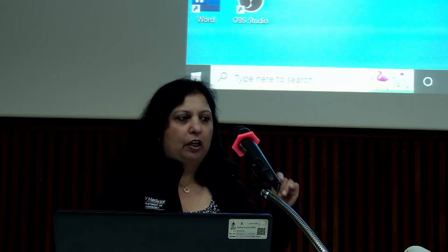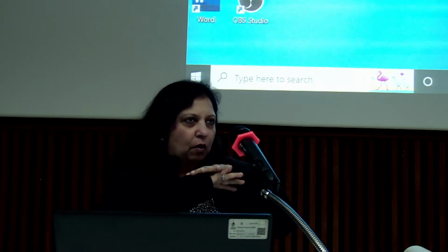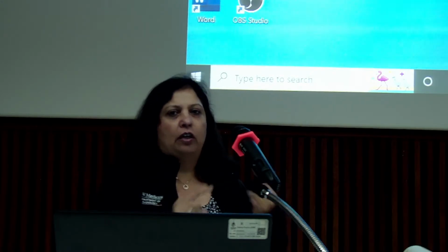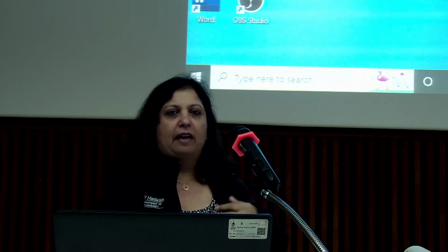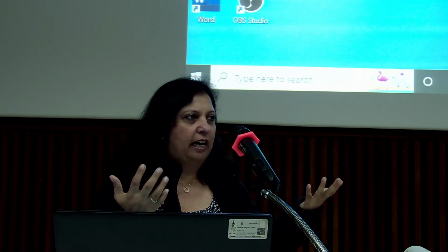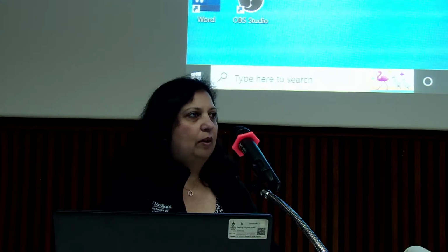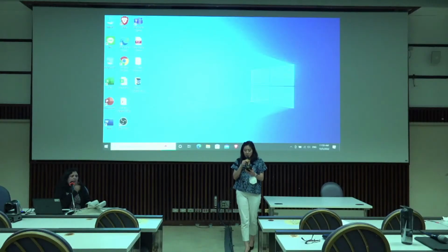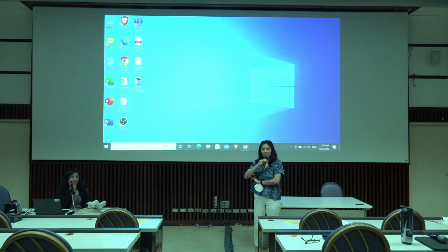There's a very good publication, NCRP 168, that's very detailed on how you can pick your thresholds, what reactions to expect, and what you should do. It's freely available, at least on the AAPM website, so you can look at it. Hopefully that answered the question. I think so, yeah. What is your setup, 2 or 1? 5 as well? For peds as well?